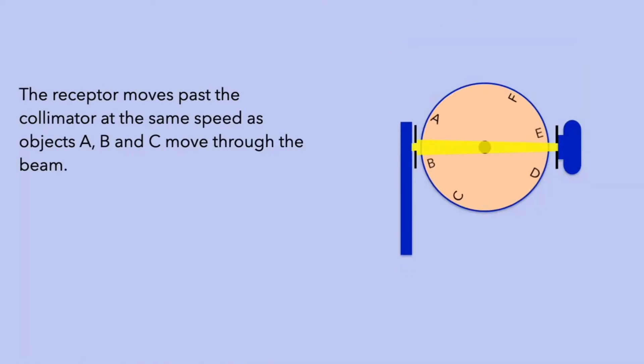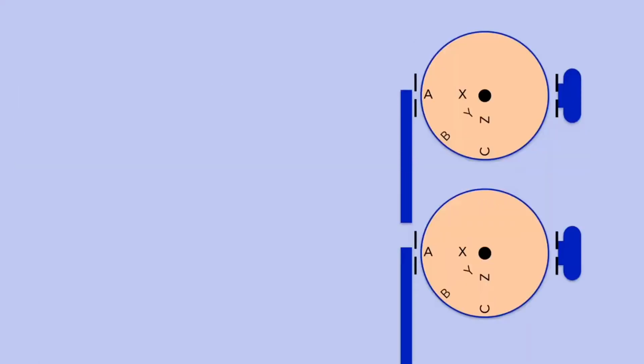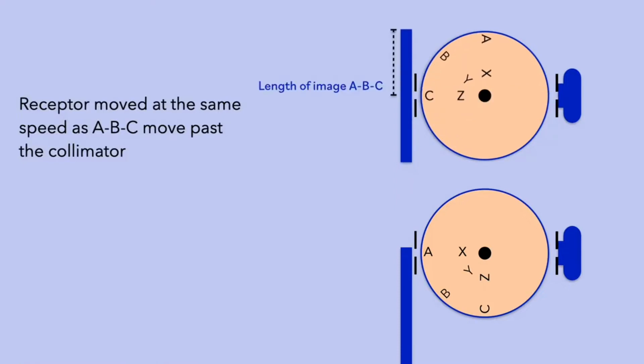Next, let's consider structures D, E, and F located on the opposite side of the disc, represented here by a square. Note that these structures are imaged in the opposite direction and that their images are markedly magnified and blurred. A key element of image layer formation is the speed of the receptor relative to the objects being imaged. When the receptor moves at the same speed as structures A, B, and C past the collimator, the length of the registered image allows structures A, B, and C to be represented with minimal horizontal distortion. In contrast, the same length of the registered image represents structures X, Y, and Z with marked horizontal distortion.